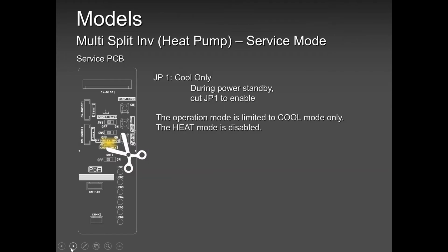Then you buy a heat pump, but now the homeowner says, I bought this heat pump only for cooling. I don't want anything to do with heat. Then again, you have the option. In this heat pump, there is a jumper outside. After you cut it, there is no more heating. You will not even see the unit going into heat mode. It will always stay in cooling. Nothing will engage. So you can use this unit without disconnecting the four-way valve or anything else. The unit will stay in cooling only.